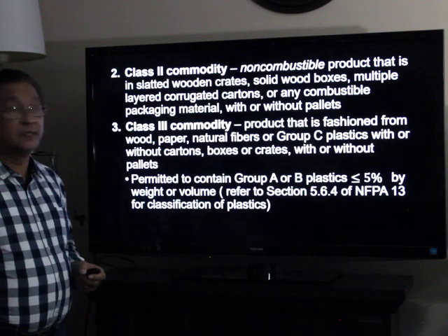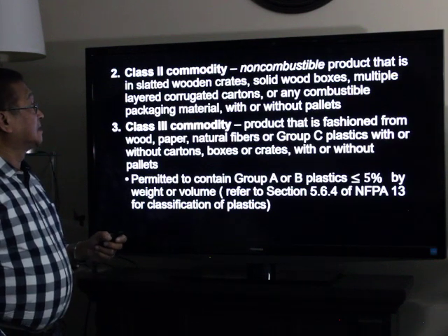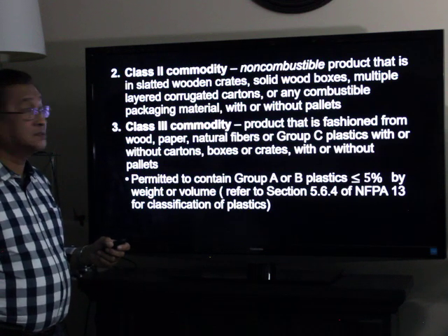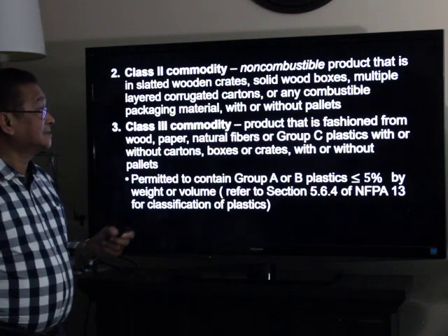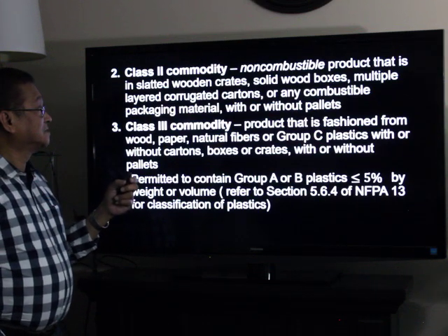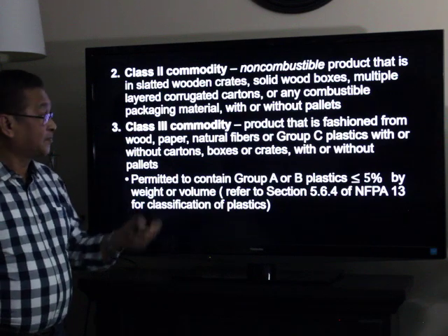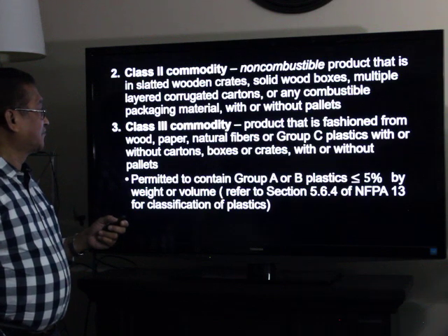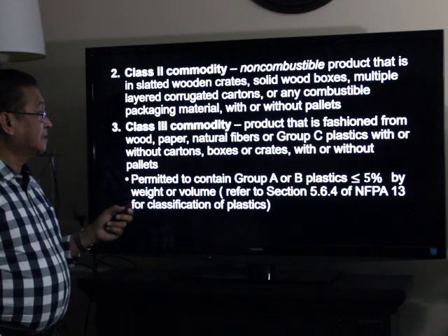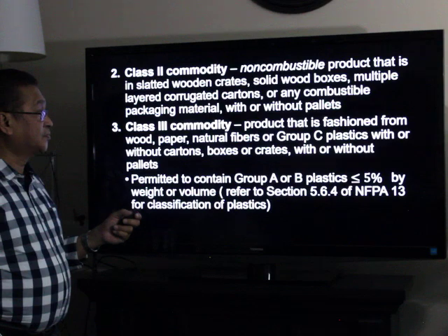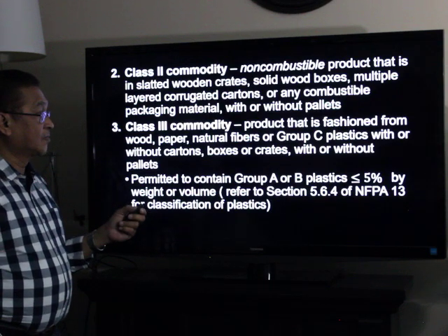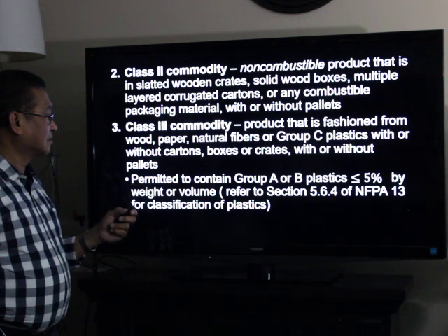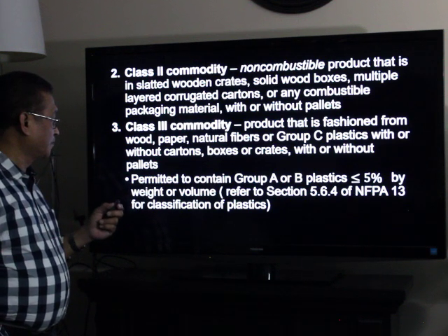Class two commodity: a non-combustible product that is in slatted wood crates, solid wood boxes, multiple-layer corrugated cartons, or any combustible packaging material, with or without pallets. Class three commodity: a product fashioned from wood, paper, natural fibers, or Group C plastics, elastomers, or rubber, with or without cartons, boxes, or crates, with or without pallets.